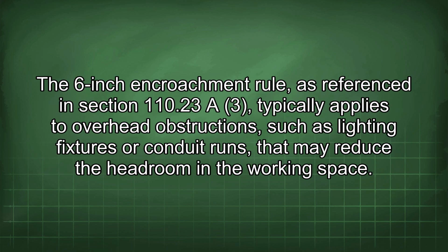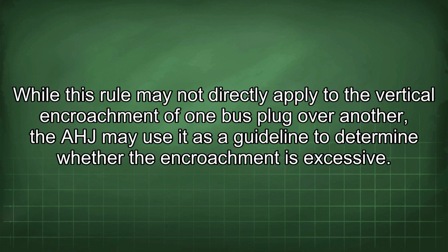The 6-inch encroachment rule, as referenced in Section 110.23(A)(3), typically applies to overhead obstructions, such as lighting fixtures or conduit runs, that may reduce the headroom in the working space. While this rule may not directly apply to the vertical encroachment of one bus plug over another, the AHJ may use it as a guideline to determine whether the encroachment is excessive.